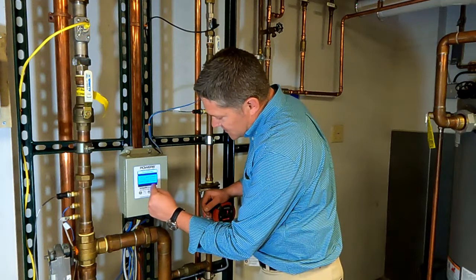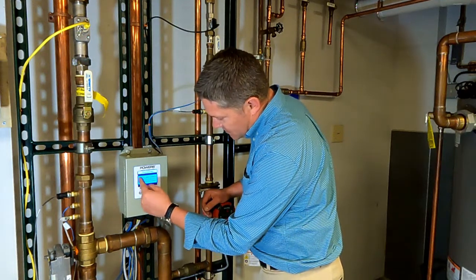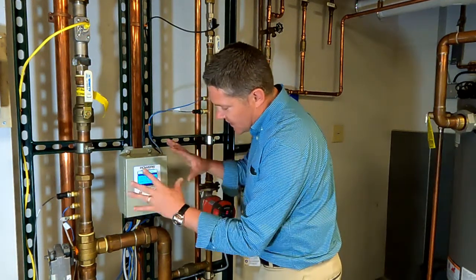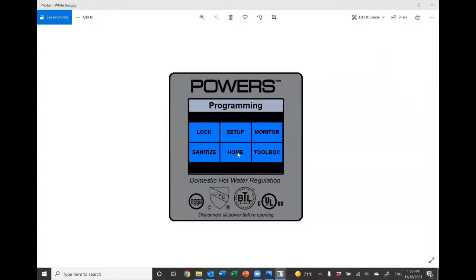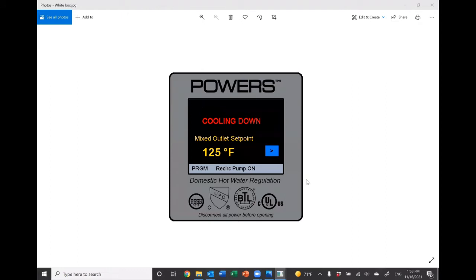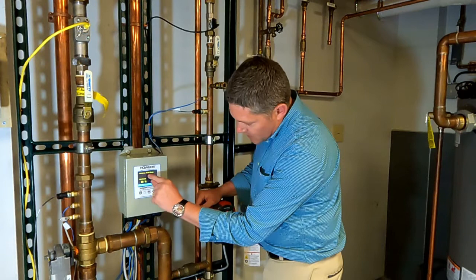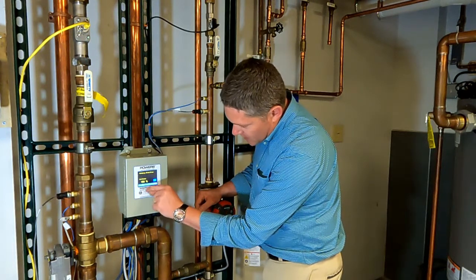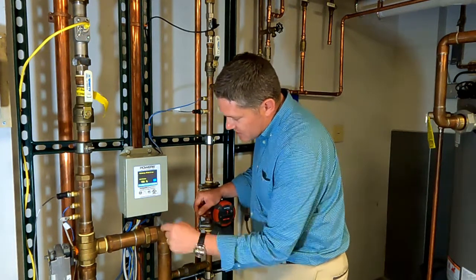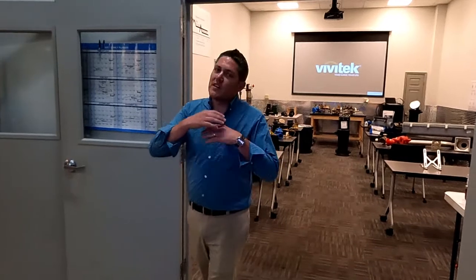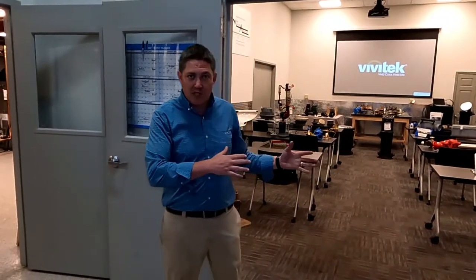There's some toolbox in here set up, and then whenever you're ready, you've got everything programmed, it's ready to operate, you can just lock the screen again, hit home screen. And like I say, it's showing you right here, I put it into sanitization mode, it's got my timer on there, and it's going to slowly start raising that temperature. So we're going to stop that. Okay, so historically, a digital mixing valve is much more expensive than a thermostatic option.